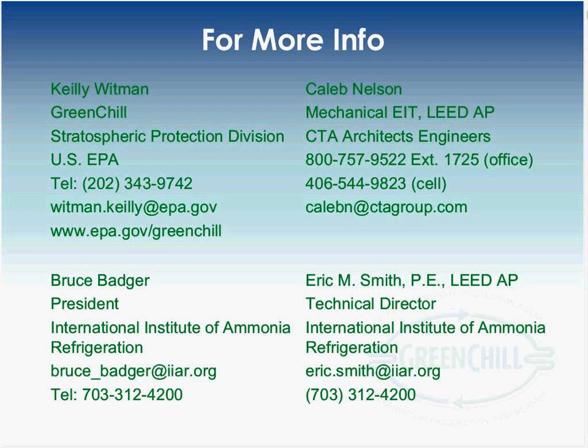Georgie, we're coming down to the end here. You have 30 seconds. Hey, I just want to make a contribution to the same topic by stating that heating of discharge and condensing heat for water heating has been broadly used in supermarkets, as a way to increase the efficiency and to supply water. And ammonia is particularly good for this because the discharge temperature with ammonia is way higher than with the other refrigerants. So if this has been used with refrigerants like 404A and 507 with much lower discharge temperatures, with ammonia it will be much more beneficial.